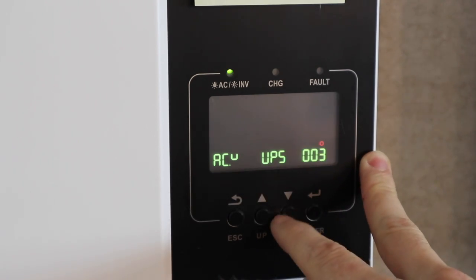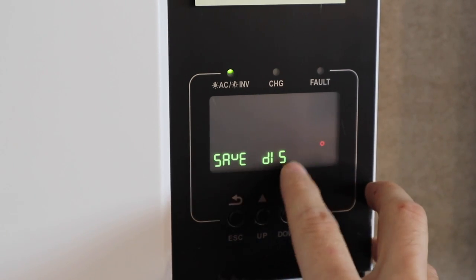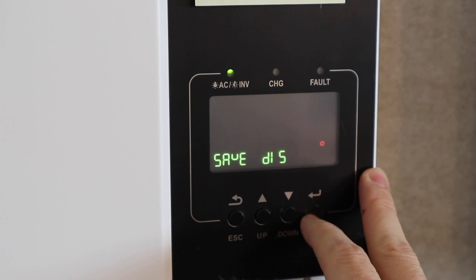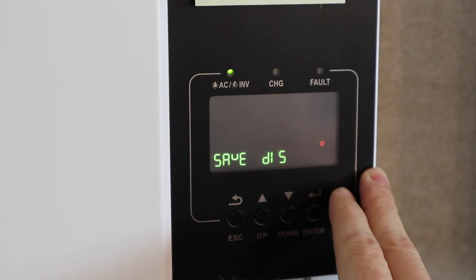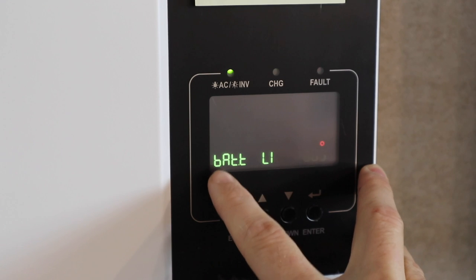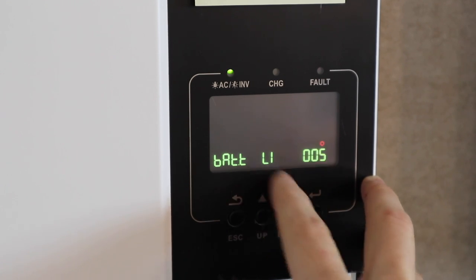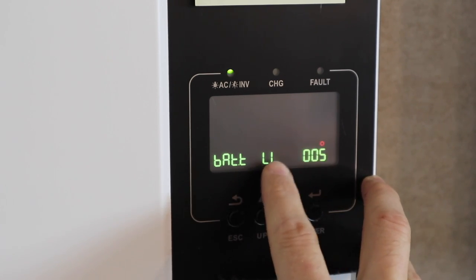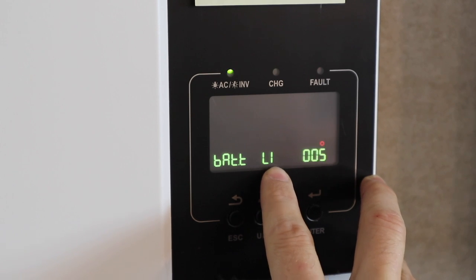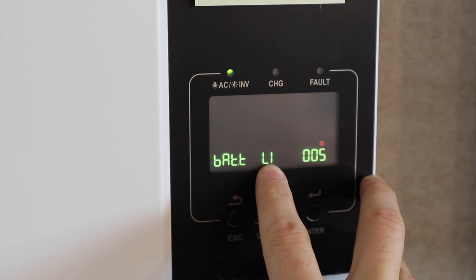So we're going to go back here. We're going to scroll down. This is disconnected setting 4. That's recommended that it stay disconnected. Setting 5 is our batteries. We just did this and set them to lithium. And you can only do that when you have the battery communication cable hooked up and the communication working properly.